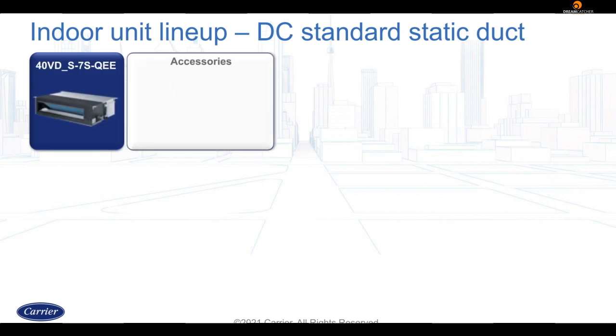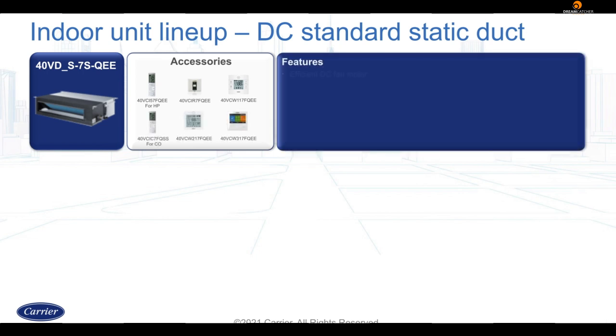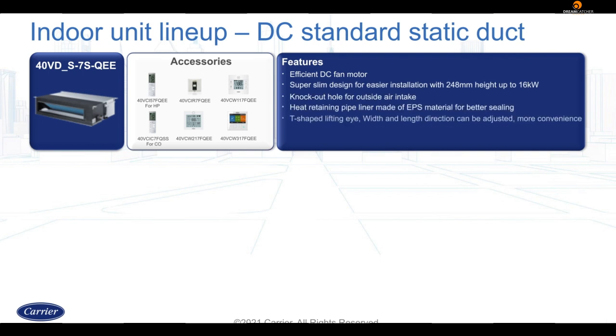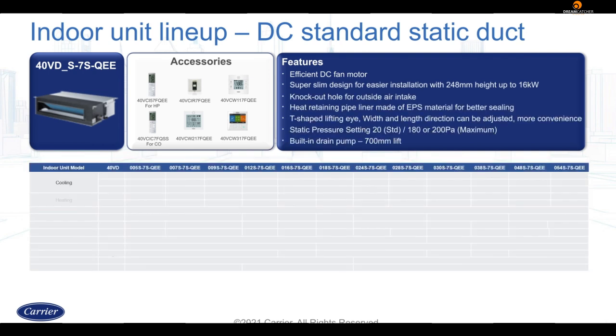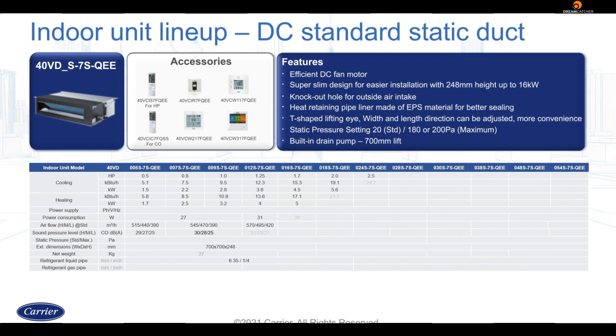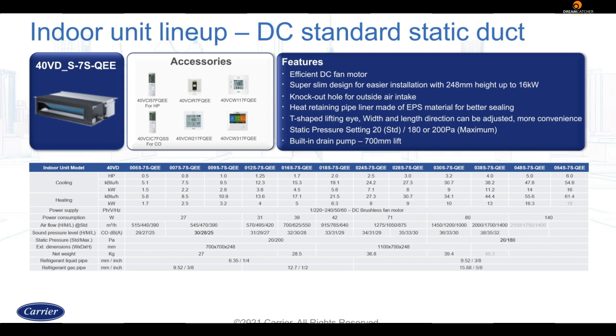The DC standard static duct comes with an efficient DC fan motor with a super slim design of 248 mm height, making it ideal for easier installation. There is also a knockout hole for outside air intake, along with a heat retaining pipe liner made of EPS materials for better sealing. It is very easy to adjust thanks to a T-shaped lifting eye and offers a static pressure setting of 180 or 200 PA. It also comes with a built-in drain pump of 700 mm lift.